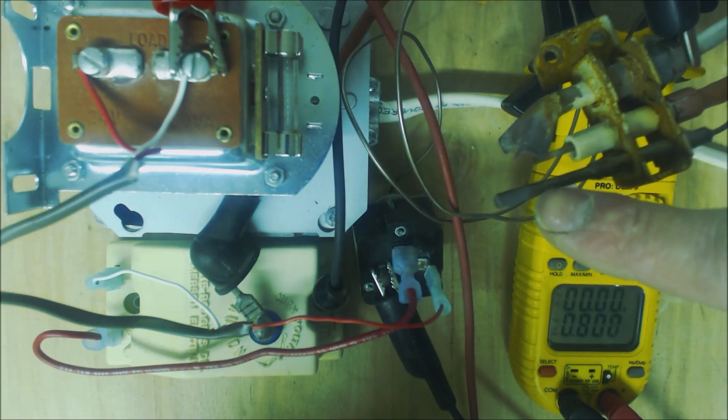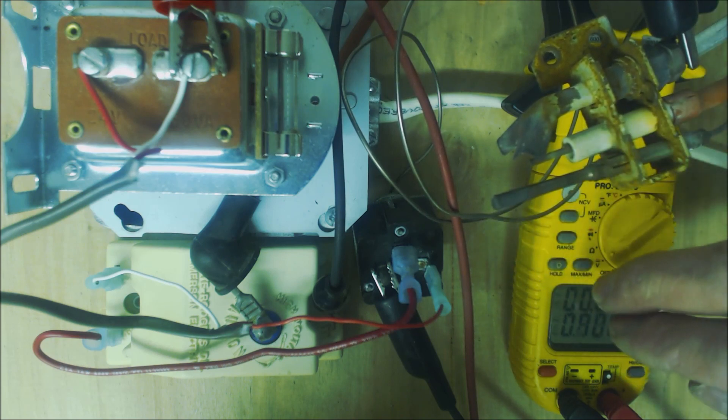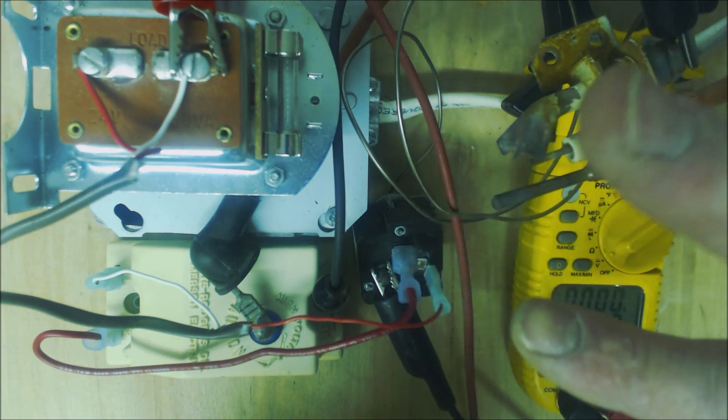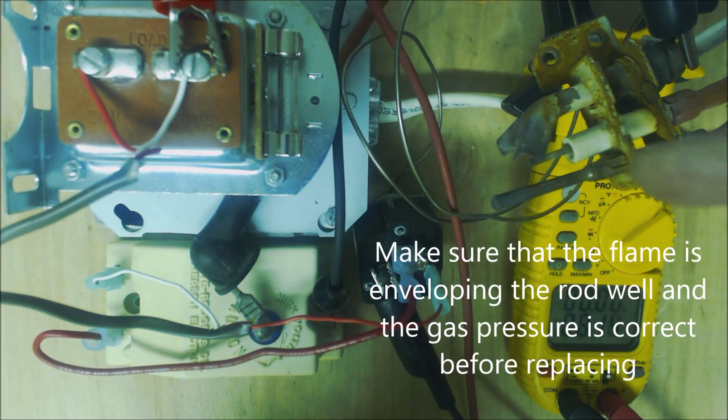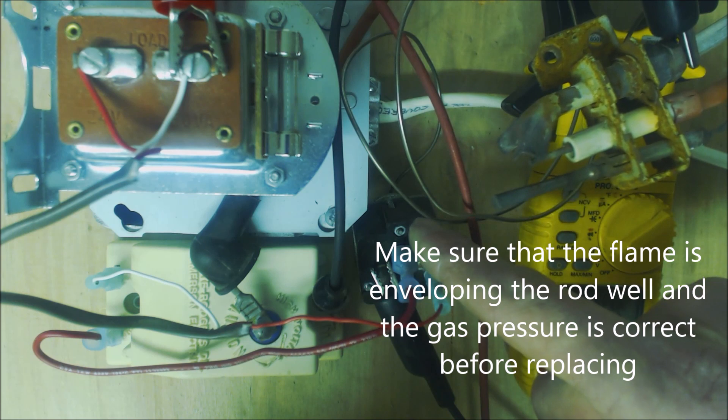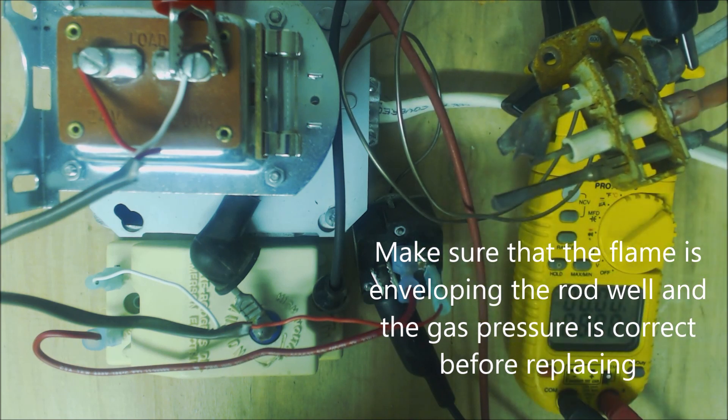If you're heating this rod up but the normally closed switch does not open and the normally open switch does not close, then you want to start looking at replacing this mercury flame sensor.